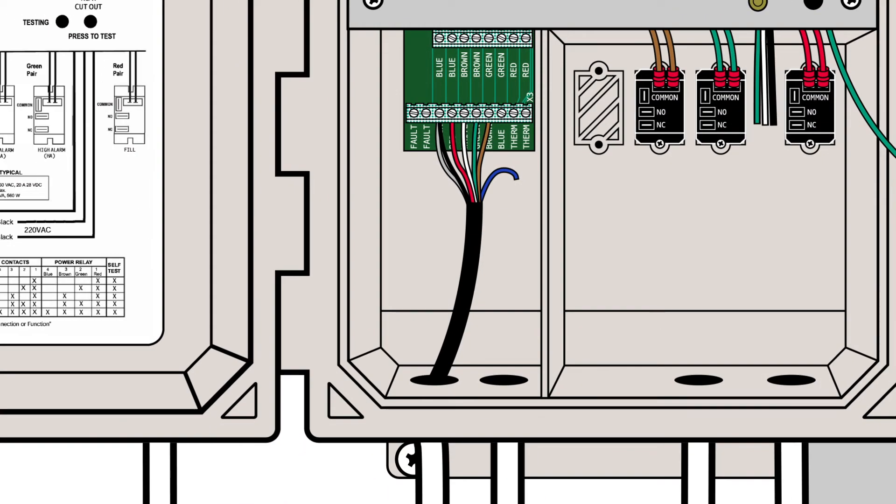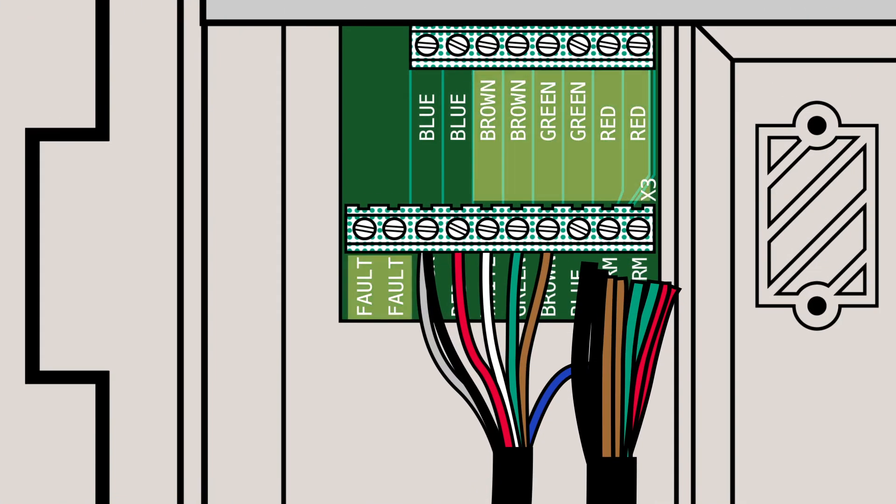The connections for the building management systems use normally open relays that close when the switch is activated. These connections come into the low voltage area and connect to the top terminal block with two positions in the lower terminal. These will indicate the state of the water level control switch points, including a power loss instance.